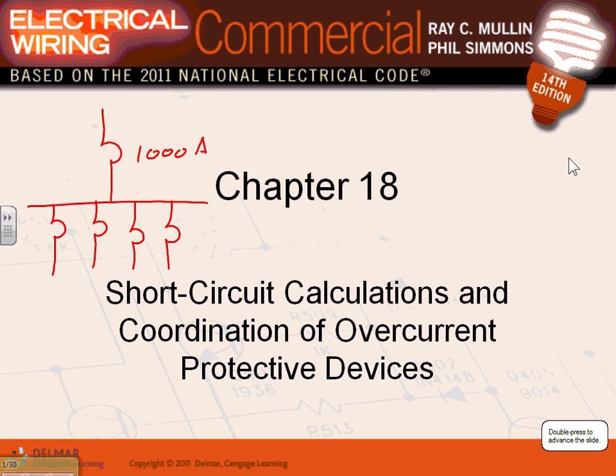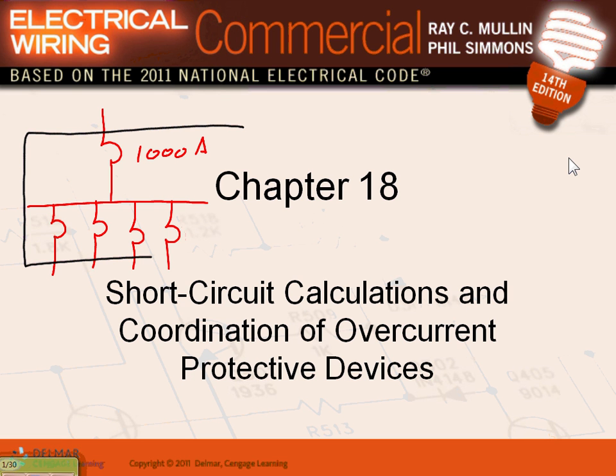Okay, so as I said yesterday, we talked about the interrupting rating for overcurrent detection devices. Today we're going to talk about the withstand rating of equipment as well as the short circuit calculation. These are engineering topics, as I mentioned. Take a 1000 amp switchgear. Now you guys have a 1000 amp switchgear, right? Inside this switchgear, you're going to have three short circuit ratings.